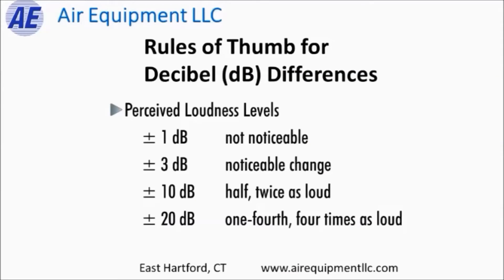A little rule of thumb with decibels: if the difference in loudness is plus or minus one decibel, that's not noticeable — the human ear can't differentiate those very fine differences. If the level differs by plus or minus three decibels, that is noticeable. Keep that in mind when reviewing submittals: if equipment submitted has a decibel level one decibel louder than specified, it won't be a problem. However, if it's three or more decibels louder, it might be a problem and you may have a noise complaint in the space.